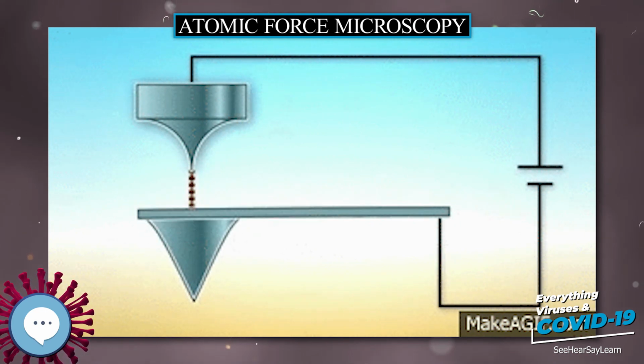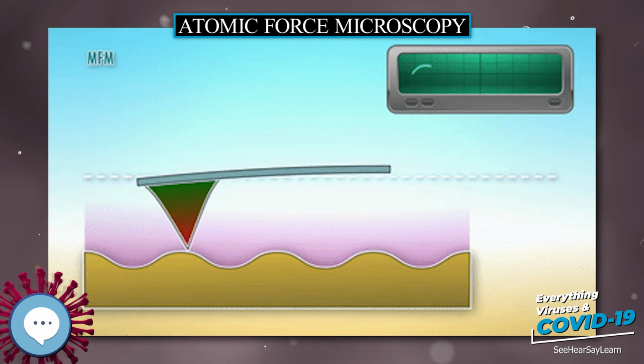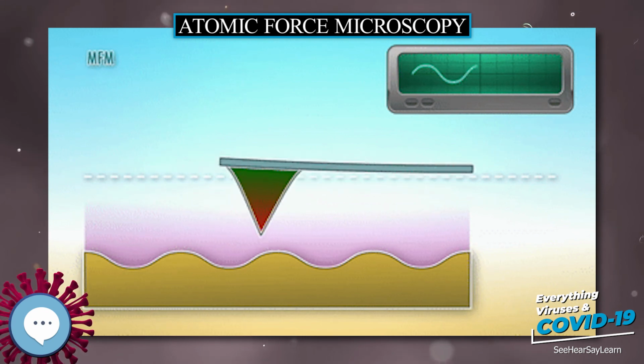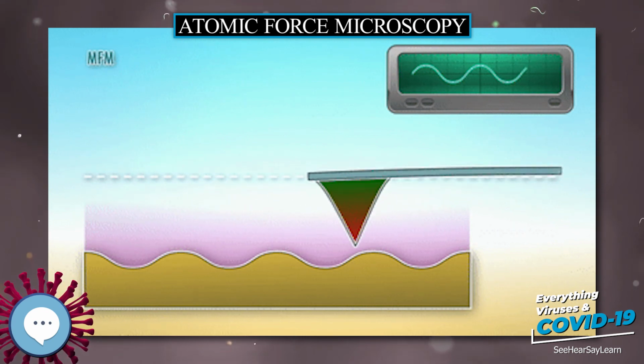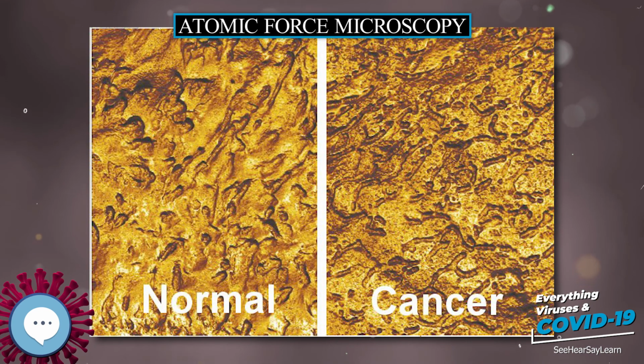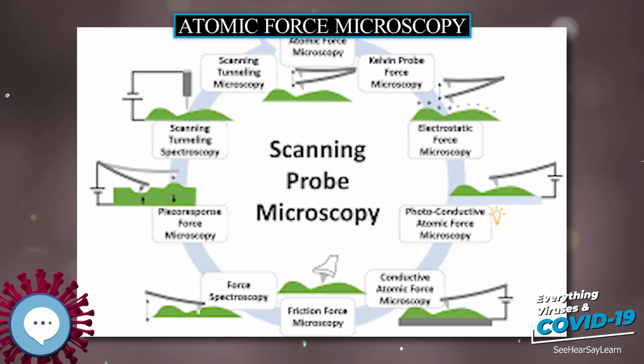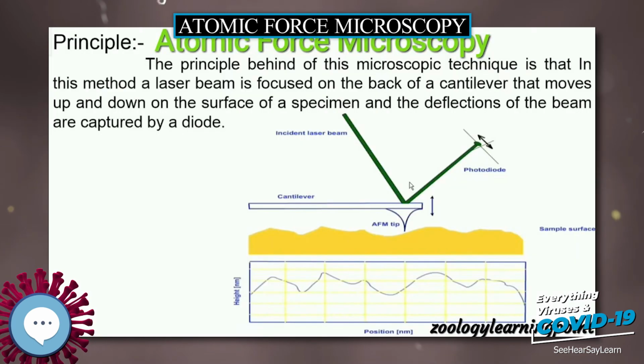Principles. The AFM consists of a cantilever with a sharp tip, probe, at its end that is used to scan the specimen's surface. The cantilever is typically silicon or silicon nitride with a tip radius of curvature on the order of nanometers. When the tip is brought into proximity of a sample surface, forces between the tip and the sample lead to a deflection of the cantilever according to Hooke's law.